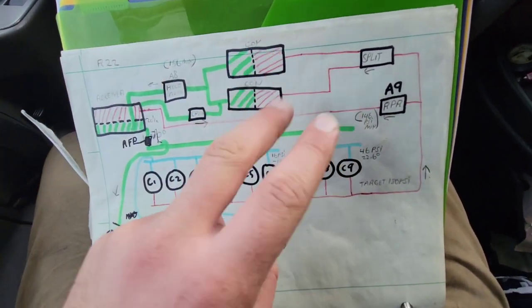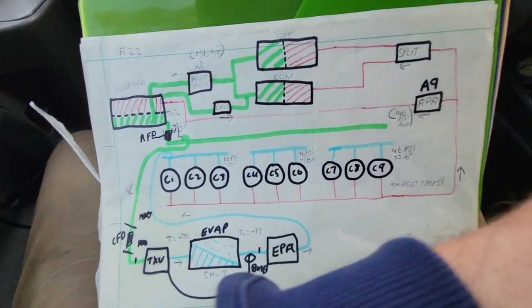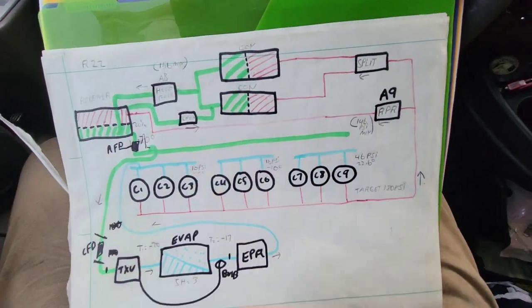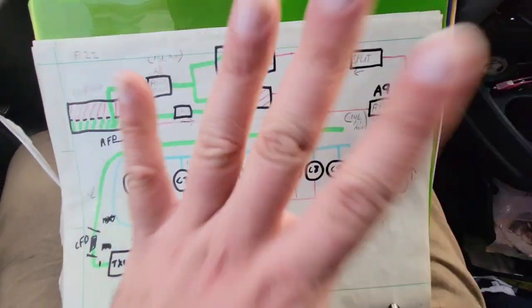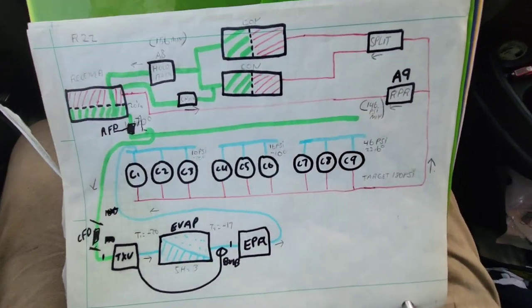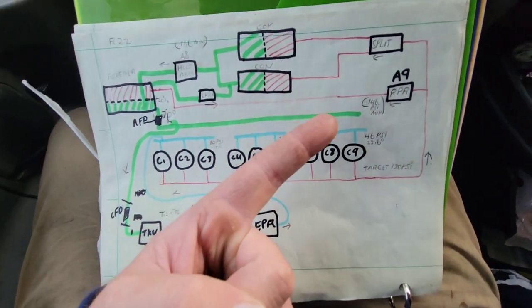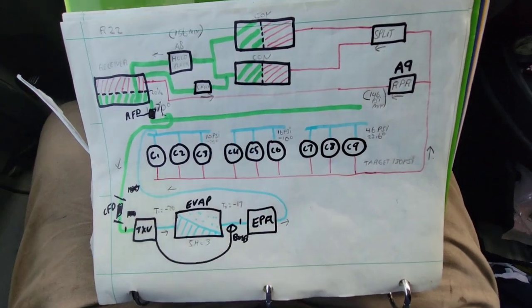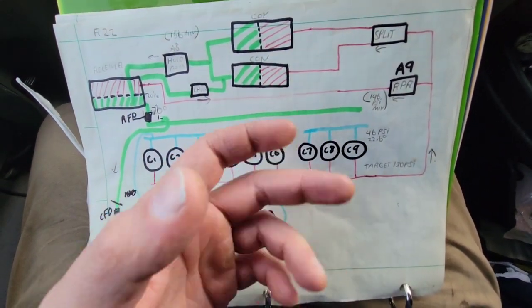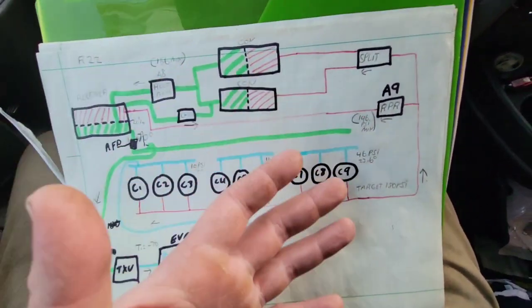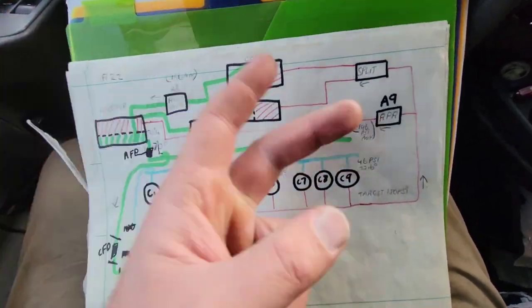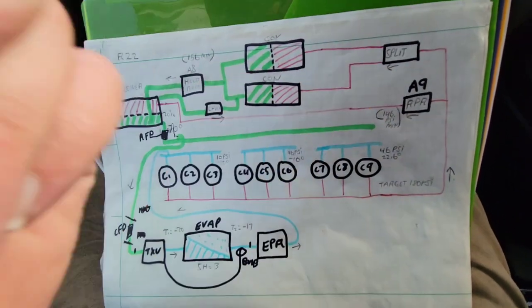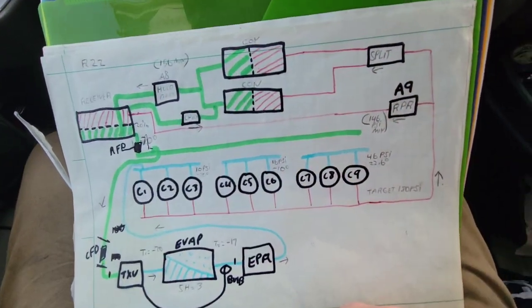Second off, temperature probe. Why do you check your temperature probe? Because you have an assumption: my case is running warm. Until you verify that temperature probe, you don't know that for a fact. You just assume that it's true, so you can't move forward. So if you pass the airflow test and the airflow is fine, and then you go to your temperature probe and think, I'm just going to assume it's working, no, you need to check it. Now you can say, my airflow is okay, but I really do have a problem. Then you can move on to your next thing.